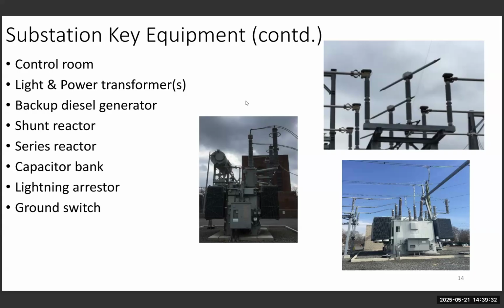I mentioned voltage control as an issue. So when the voltage is too high, if equipped, we energize a device called a shunt reactor. You could see the picture on the left. That's what it looks like. It's an oil-filled shunt reactor. The opposite to that is something called a capacitor bank. I may have a picture later. That's a device to supply reactive power. So shunt reactor lowers the voltage, cap bank raises the voltage.